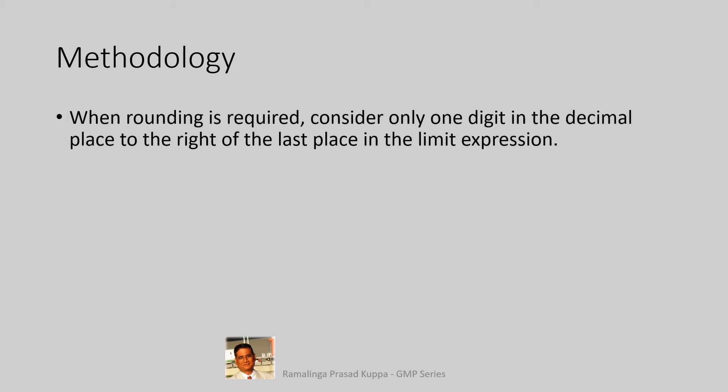Let us see the methodology and requirements for rounding off results. When rounding is required, consider only 1 digit in the decimal place to the right of the last place in the limit expression. This point should be understood well. If there are 2 digits after the decimal point in the specifications, you have to select 1 more digit on the right side next to the 2 specification digits. That means, you have to select total 3 digits after the decimal point. The same principle holds good for any other numbers.